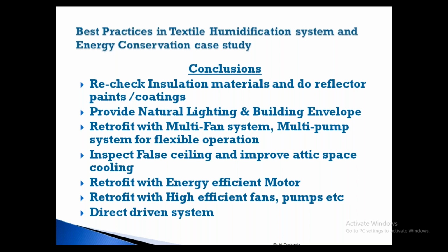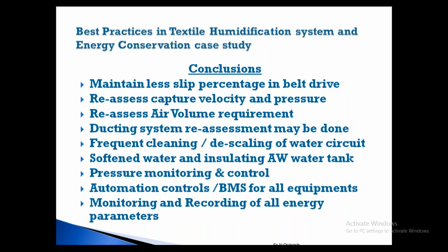So retrofit high efficient fans. In this area there is a lot of scope. Then pumps, changing pumps also has a lot of scope. Direct driven system I also explained already. So direct driven system wherever possible, otherwise there will be slippage if it is a belt system. Maintain less slip with the belt drive system. How to reduce the slip of the belt? Types of belt, that is cogged belt and different belts are there.